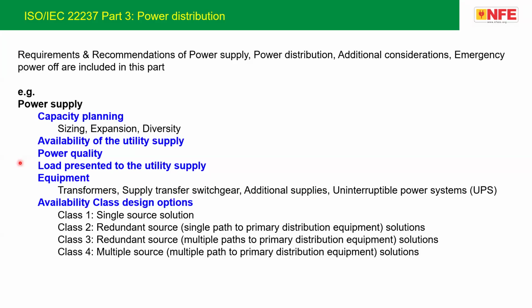When we move to the supply transfer switch, in India there is no general practice for synchronization of the system. So we should take care that the supply transfer is automatic, not manual, in case of main power failure, and we have to monitor that also. For that we have to select LV and HV equipment complying with IEC requirement 62271. We have to go for open transition, because in India there is no practice of synchronization with the utility supply. So there should be a delay within the transfer when we transfer the supply from one source to another source.